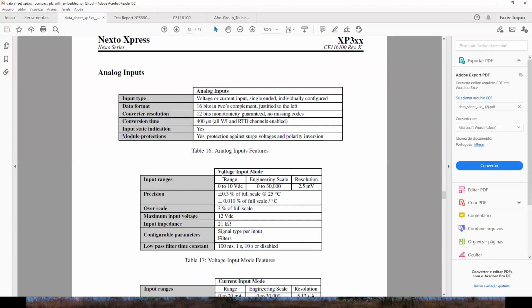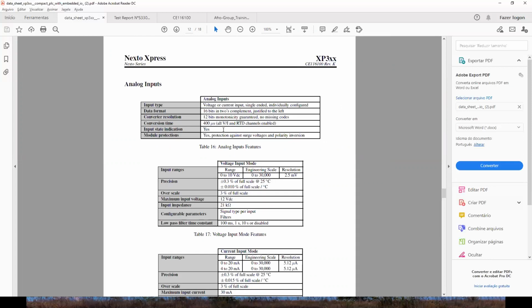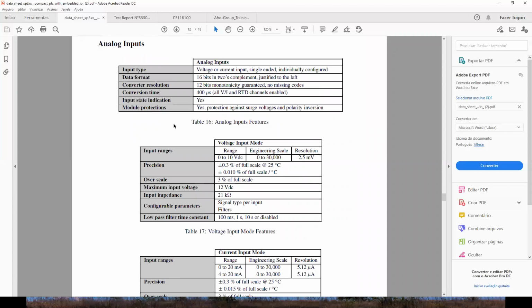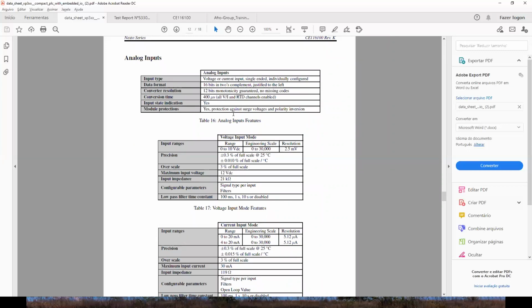So it's very fast because, as you know, the hardware is very fast and very strong. We can run, for example, the main task in this hardware in about 5 milliseconds. So to collect and digitize the information from the field to the hardware, we are very fast. Now talking about the protocol. To send this information through our Ethernet port or serial, well, now we don't have BACnet, so we can talk about the protocols that we have here, and as they are totally standardized, we need to follow these standards. For example, our Modbus RTU, our Modbus TCP or our OPC UA.